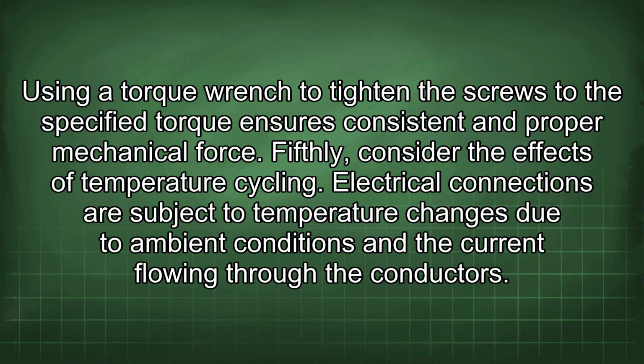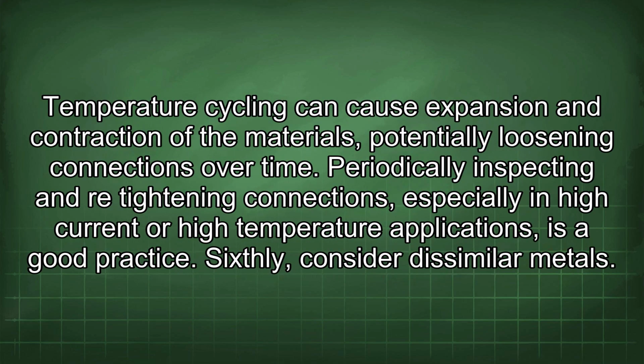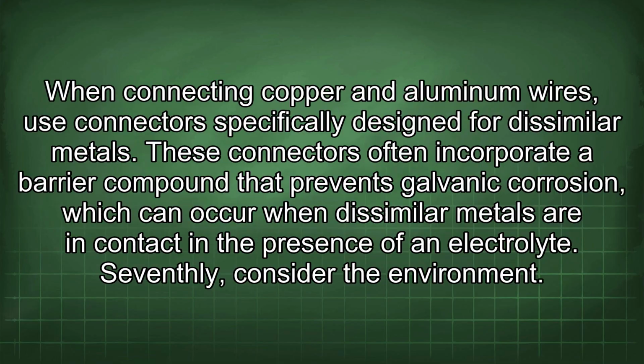Fifthly, consider the effects of temperature cycling. Electrical connections are subject to temperature changes due to ambient conditions and the current flowing through the conductors. Temperature cycling can cause expansion and contraction of the materials, potentially loosening connections over time. Periodically inspecting and retightening connections, especially in high current or high temperature applications, is a good practice. Sixthly, consider dissimilar metals. When connecting copper and aluminum wires, use connectors specifically designed for dissimilar metals. These connectors often incorporate a barrier compound that prevents galvanic corrosion, which can occur when dissimilar metals are in contact in the presence of an electrolyte.